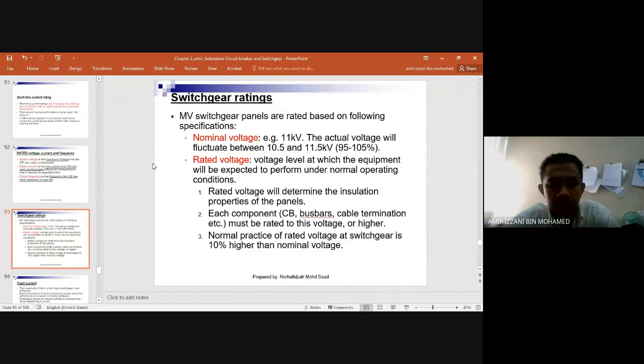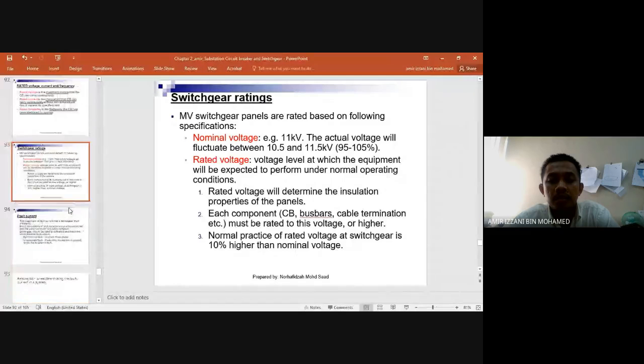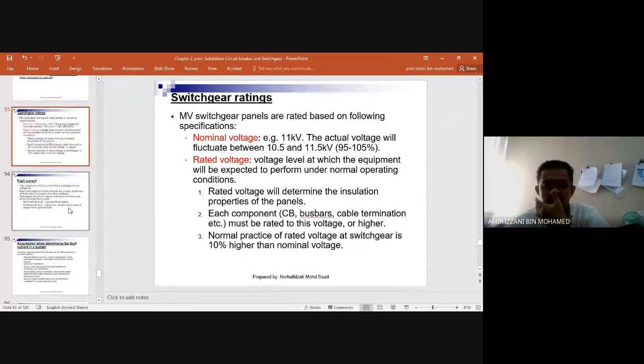So what is rated voltage? It is the voltage level at which the equipment will be expected to perform under normal operating condition. Rated voltage will determine the insulation properties of each component, CB, bus, cable termination, etc. Each must be rated to this voltage or higher. Normal practice of rated voltage at switchgear is 10% higher than the nominal voltage.